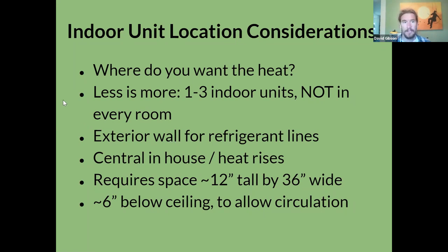Generally, you want to mount the indoor unit on an exterior wall so that the refrigerant lines can go out through the wall and then run on the exterior of the house. I've seen some cases where it works to build an interior chase or run them up or down to the basement or up to the attic in a stairwell or that sort of thing. But usually, again, the more complicated the installation, the more expensive the system is going to be. So if you are trying to find a complicated place to put them, it will cost you more upfront.